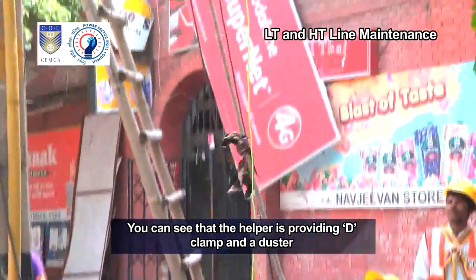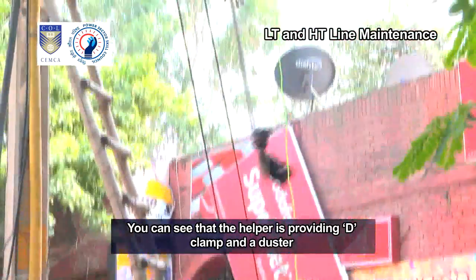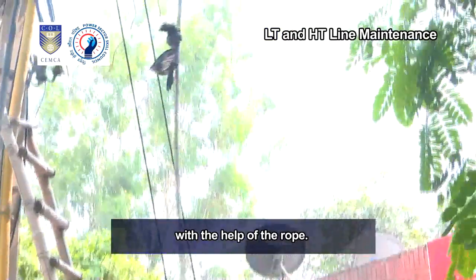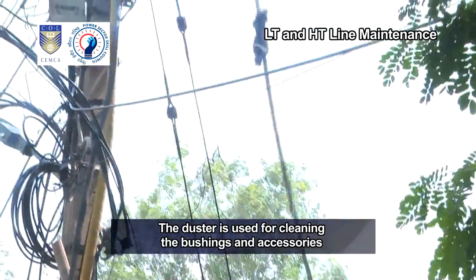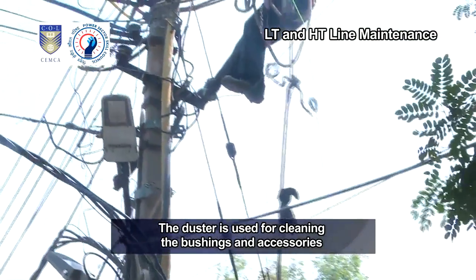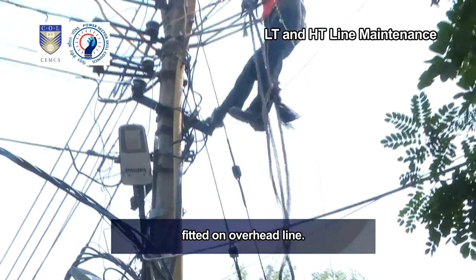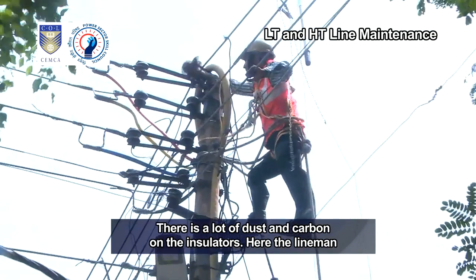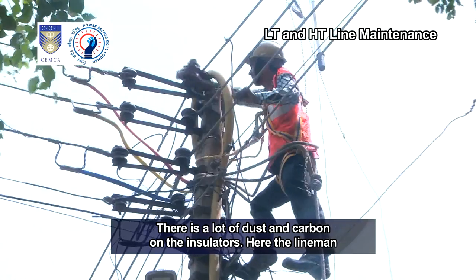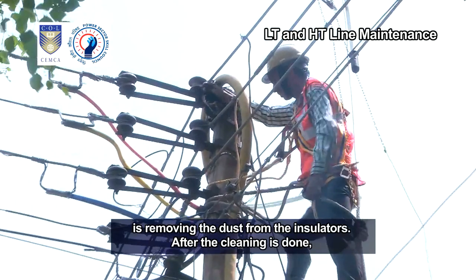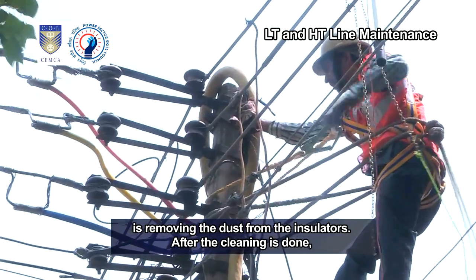You can see that the helper is providing D-clamp and a duster with the help of the rope. The duster is used for cleaning bushings and accessories fitted on overhead line. There is a lot of dust and carbon on the insulators. Here, the lineman is removing the dust from the insulators.